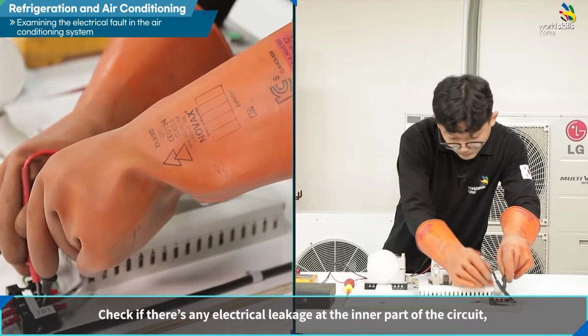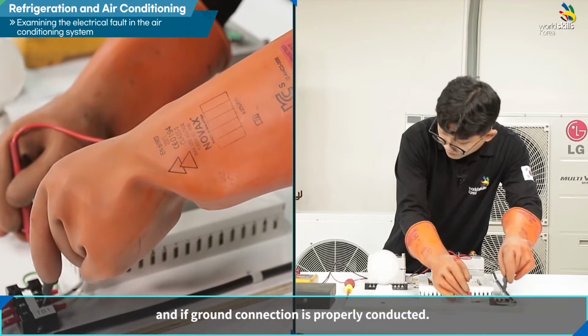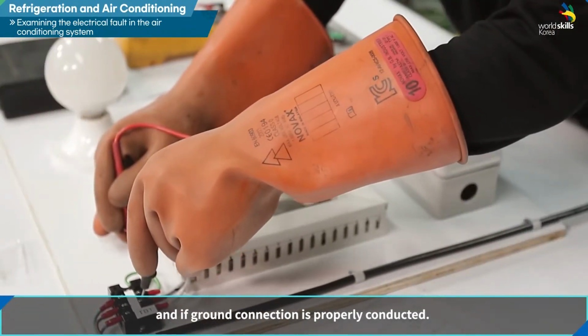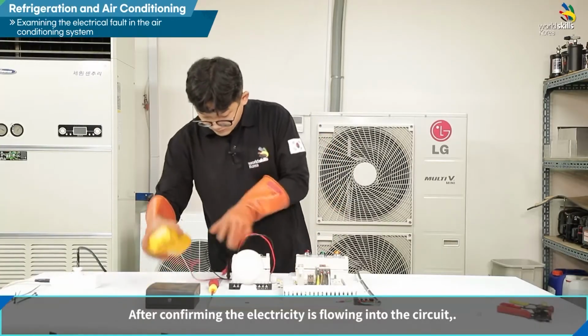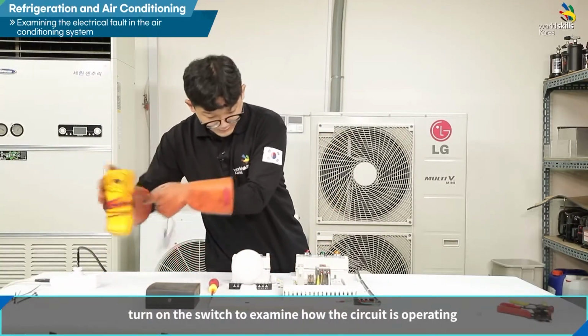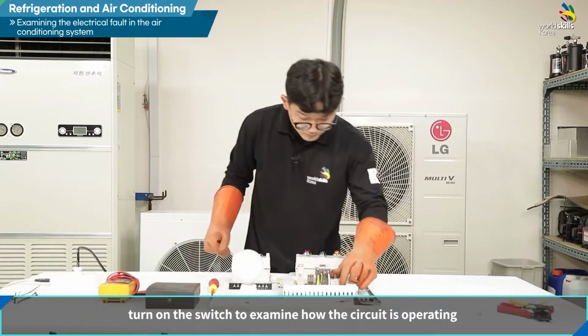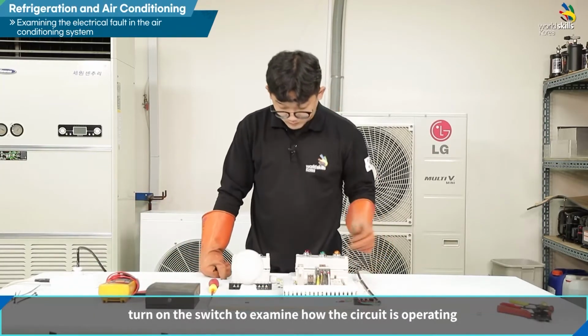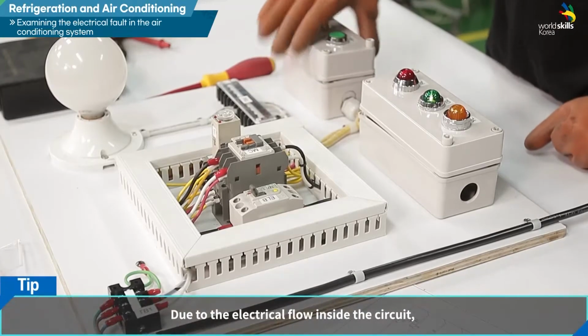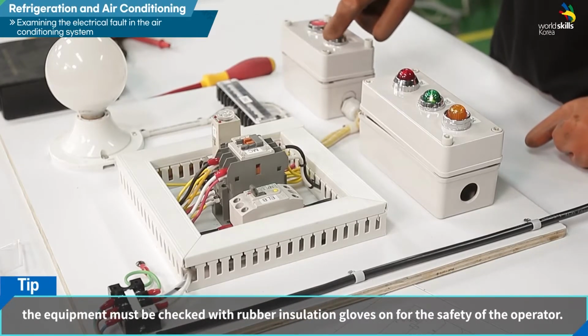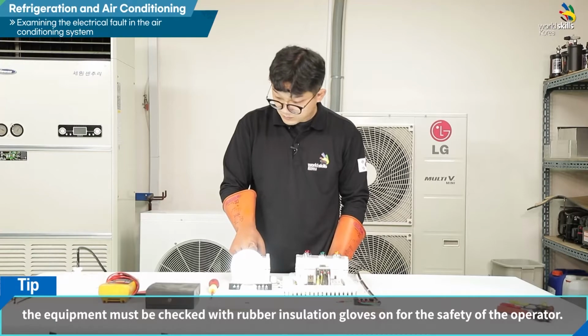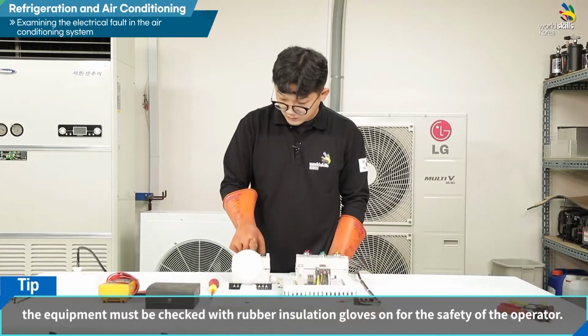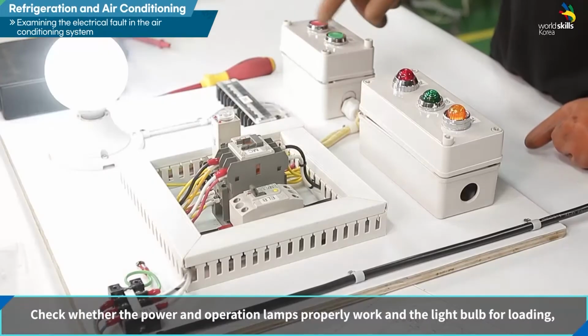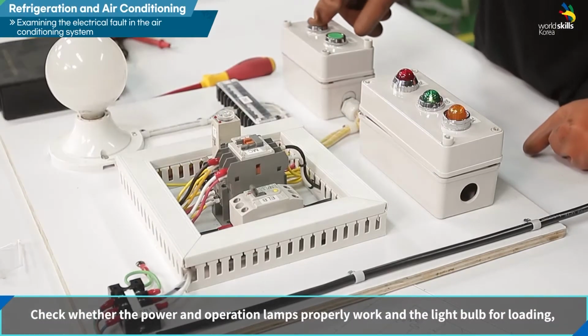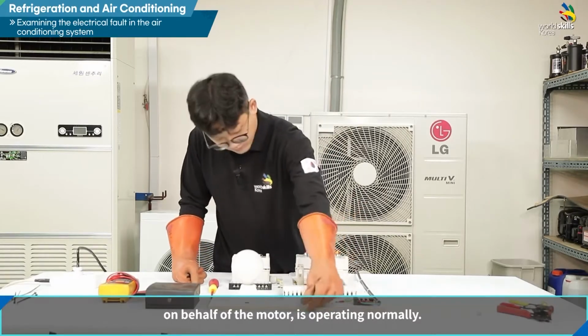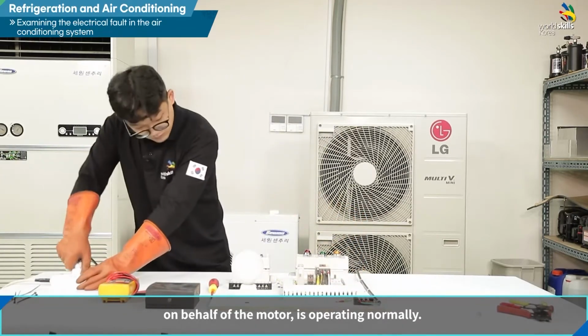Check if there's any electrical leakage at the inner part of the circuit and if ground connection is properly conducted. After confirming the electricity is flowing into the circuit, turn on the switch to examine how the circuit is operating. Due to the electrical flow inside the circuit, the equipment must be checked with rubber insulation gloves for the safety of the operator. Check whether the power and operation lamps properly work and the light bulb for loading on behalf of the motor is operating normally.